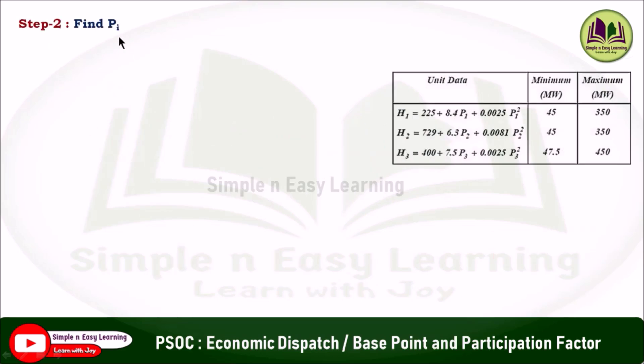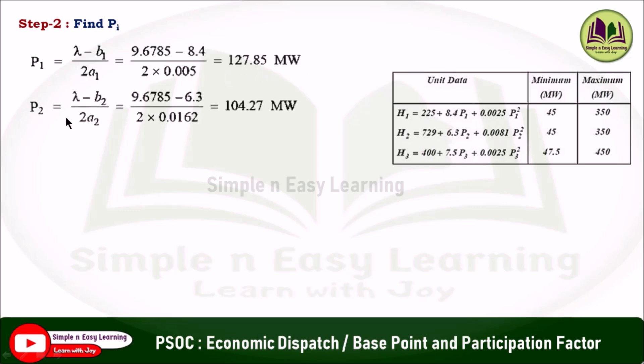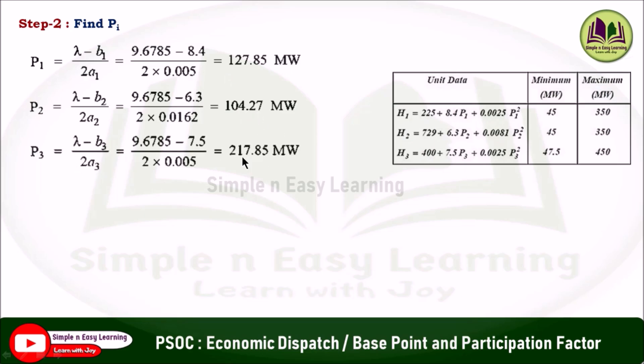Step 2: Find the power generation P_i for all three units. The formula is P_i = (lambda − b_i) / 2a_i. For unit 1: P1 = (lambda − b1) / 2a1. Substituting lambda from the previous step and b1, a1 from the cost function gives P1 = 127.85 megawatt. Similarly, P2 = 104.27 megawatt and P3 = 217.85 megawatt.